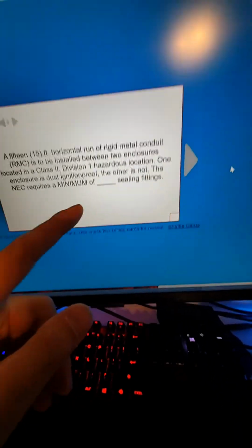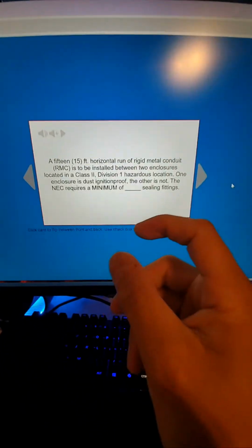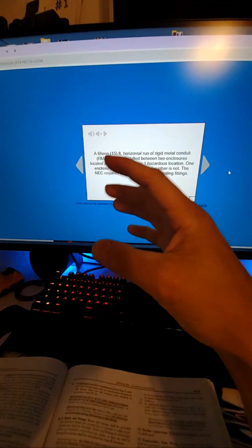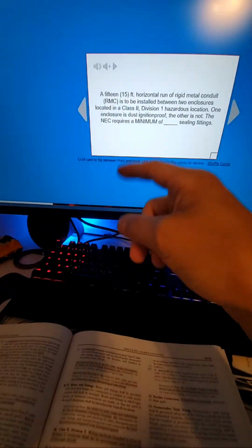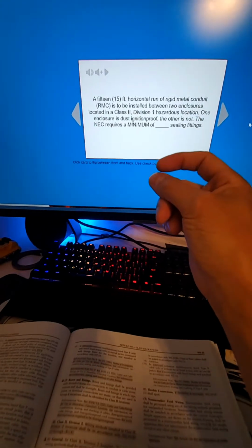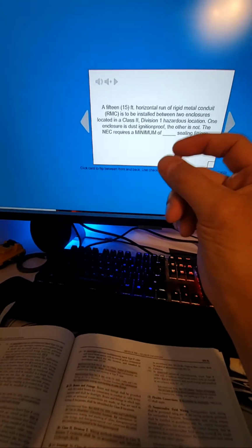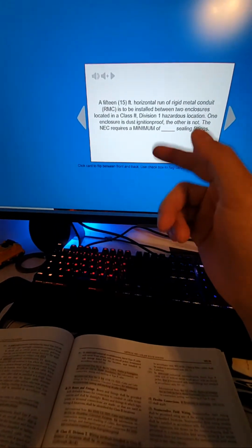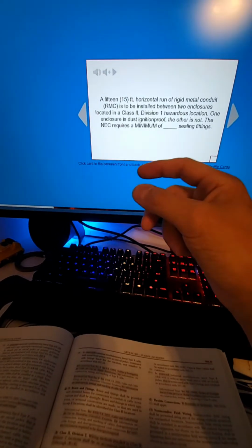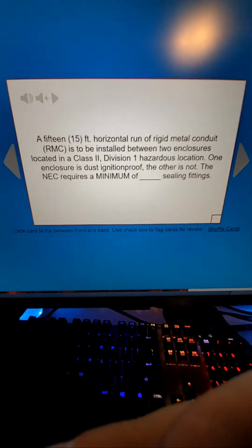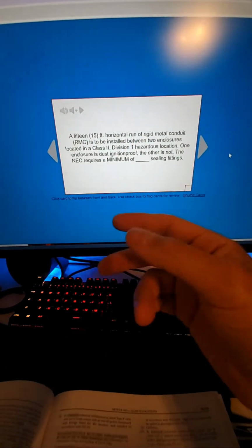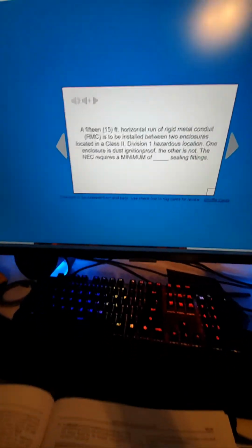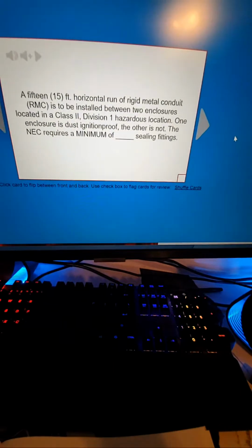So the idea of sealing fittings, if you know what they're for, it helps you understand what they're asking. Seal off fittings are almost like a T, if you think of it that way. It's not a T, but think of it like a T, where you've got one opening at the top, one opening at the bottom, and then you've got a spot where you can put a sealing material. Typically it's called Chico, and it hardens up like rock. You mix it up and you pour it into the conduit, and it seals off the vapors between the different classes of locations. Like your gas pump would have gas vapors, and you don't want those vapors going back to your panel where you could have a spark. So the seal off fittings, it's probably going to ask us, we got to figure out how many fittings we need.